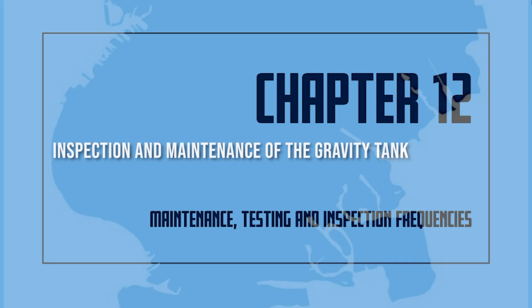Inspection and maintenance of the gravity tank. The gravity tank should be regularly inspected and maintained in accordance with the NFPA number 25, 2002 edition. Maintenance is needed to be sure that the tank functions correctly. Tanks are to be painted regularly to prevent rusting. Before the inside of a gravity tank is repainted, the surface should be thoroughly dried. All loose paint, rust, scale, and other surface contamination should be removed. The outside of the gravity tank will require local patching. A complete finish coat of paint is needed when the paint has weathered thin. A new coat of paint also improves the appearance of the tank after it has been patched.